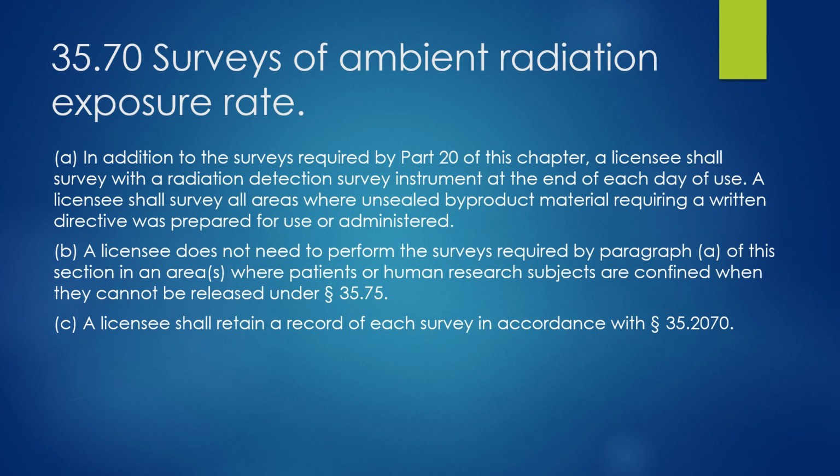And that you should survey all areas where byproduct material requiring a written directive was prepared for use or administered. And then it says you do not need to perform the surveys where patients or human subjects were confined and they cannot be released. So you would not have to go into an I-131 patient's room to survey their room at the end of the day, because you know that they're radioactive and so their room will be.